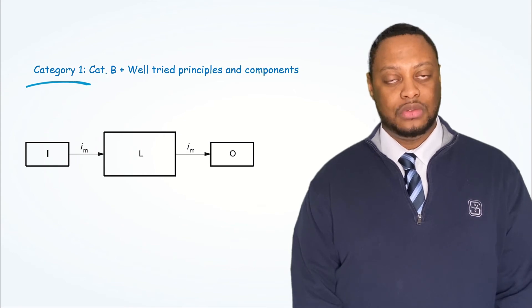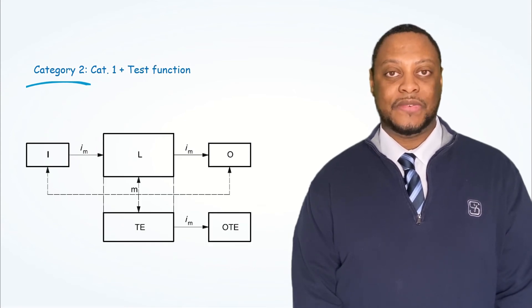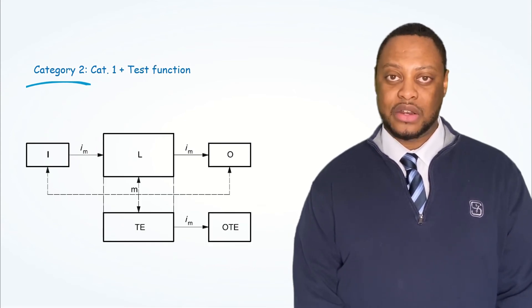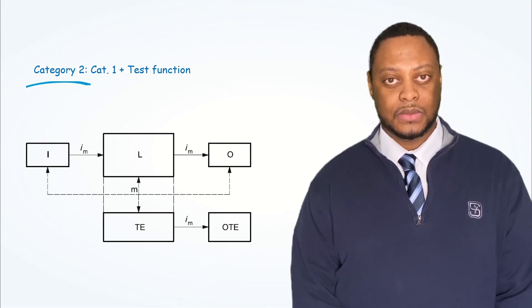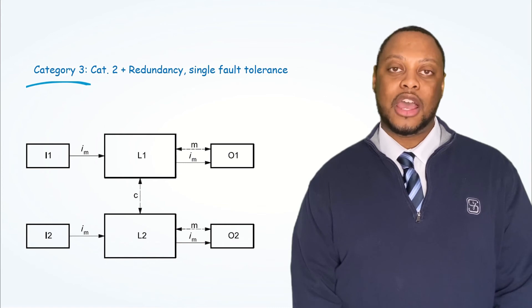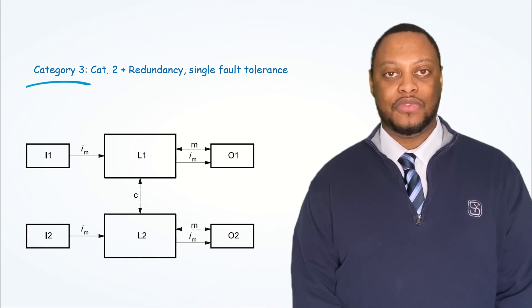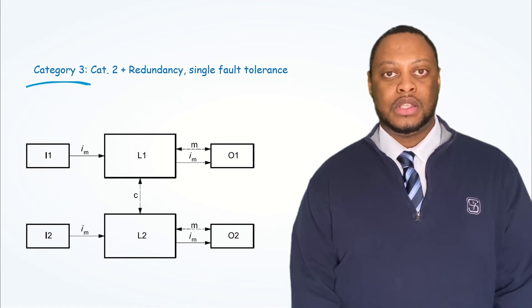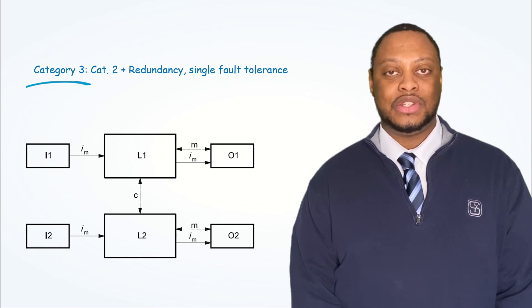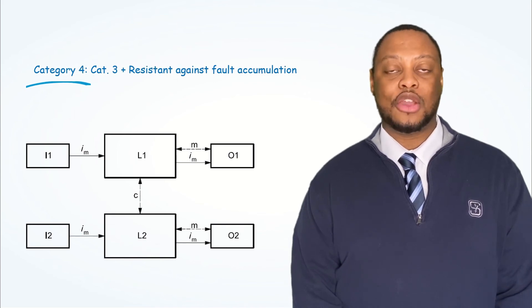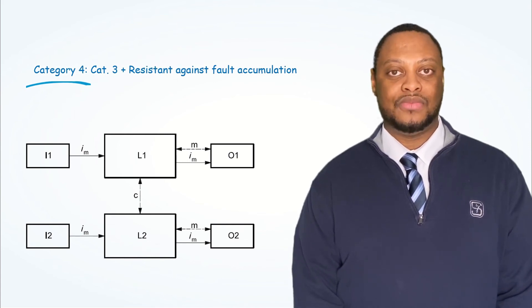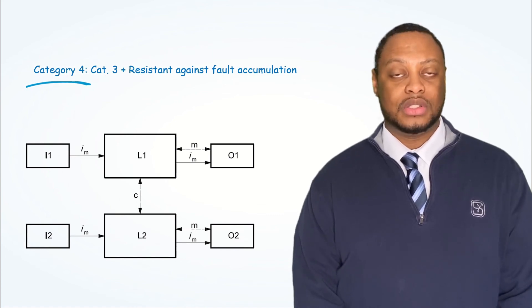Category 2 introduces a test function, still a single channel — one failure and we lose our safety function. Category 3 brings in the idea of a second redundant channel, so now we have the ability to detect a single failure and maintain safety. The last category is Category 4, which is again redundant with constant monitoring, but now we are resistant against fault accumulation.